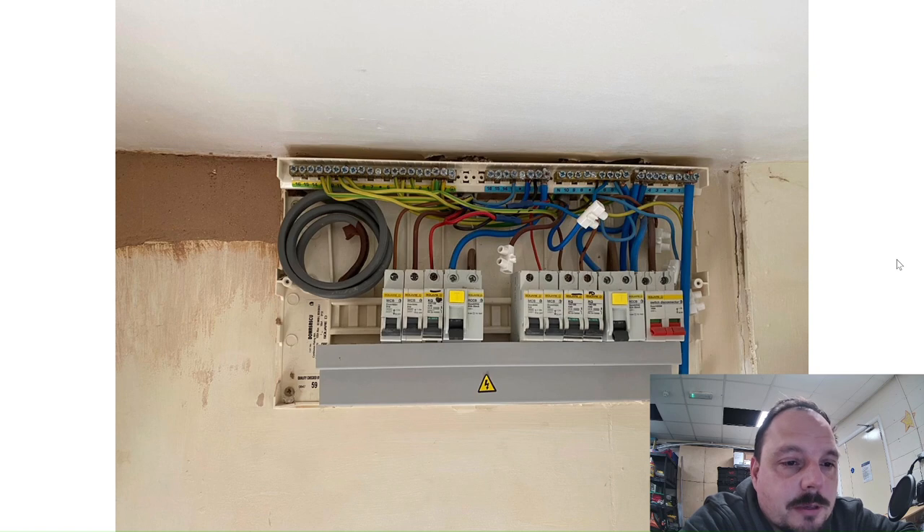A new kitchen is going in, and I'm hopeful that once it's done the client will have funds to update the board. There's nothing particularly wrong with it other than the fact it's a split-load board — I'd prefer to have RCBOs if it was my own property. Whilst you can't flag that on EICRs, you can make a case for usability and avoiding nuisance trips that turn off more circuits than necessary. The fact that it's plastic and it's over the back door isn't ideal either. The primary issue for the client was aesthetics — it looked a bit scruffy and yellow from being in the kitchen for about 20 years.